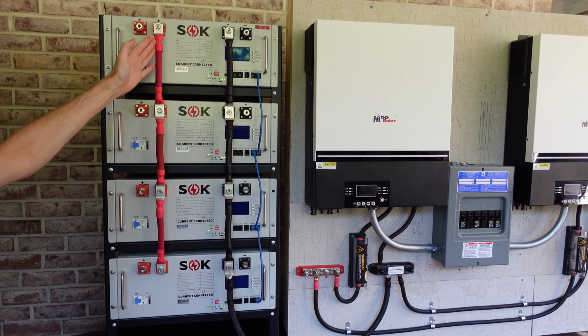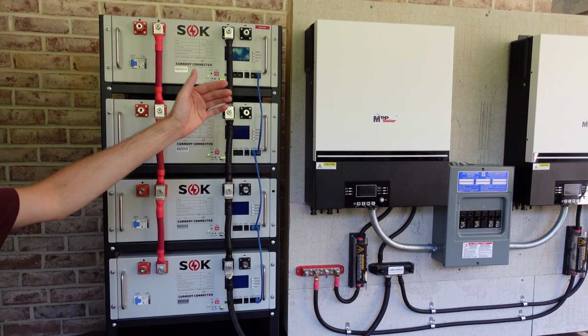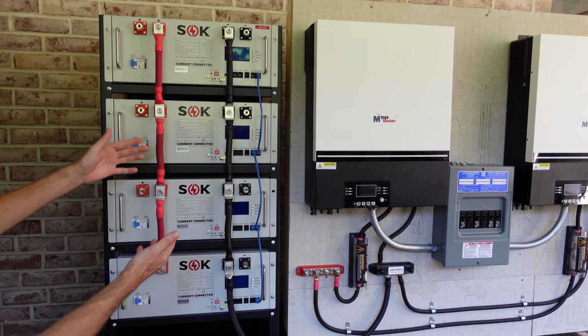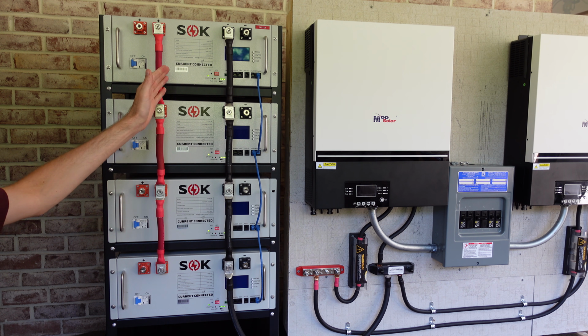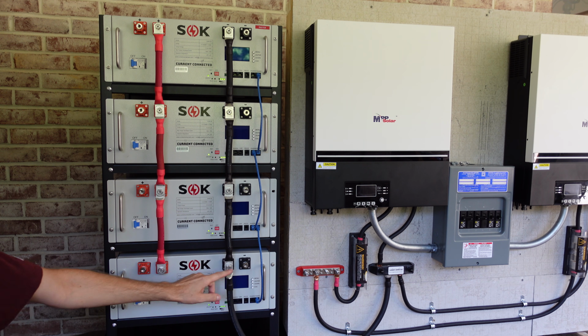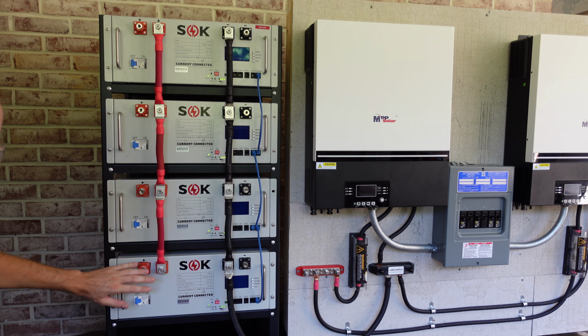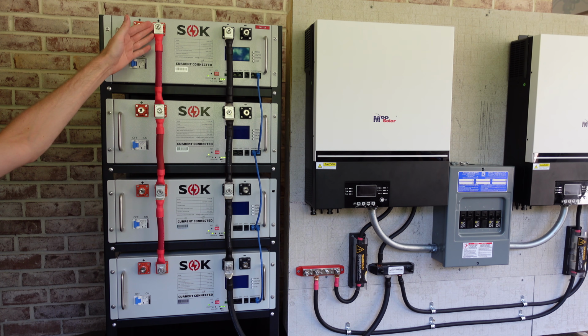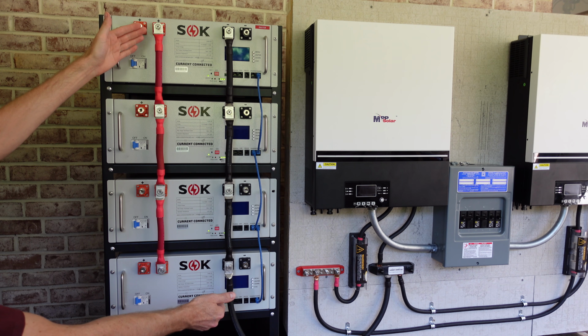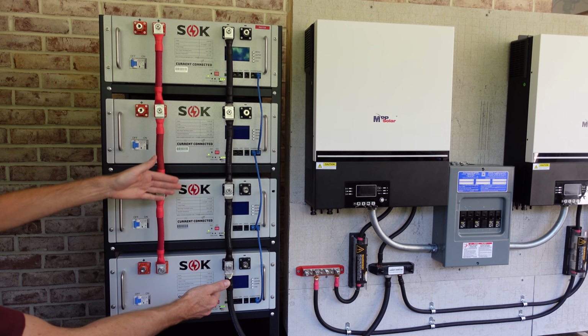And what that's going to do is basically help these inverters pull power from all of these batteries collectively. If I were to put the main positive and negative on the same battery down here, this bottom battery is going to be doing most of the work. So by making the second connection on the opposing end of the string of batteries, you can kind of see how it's pulling current through this entire battery rack.